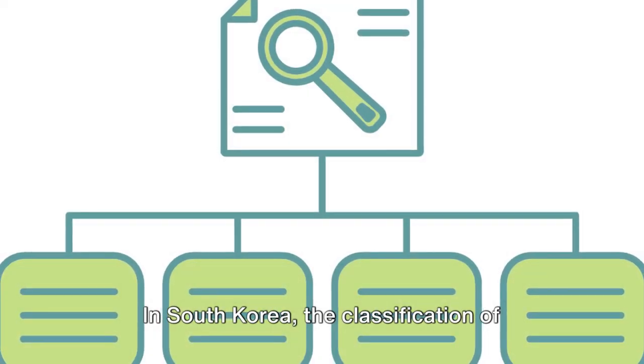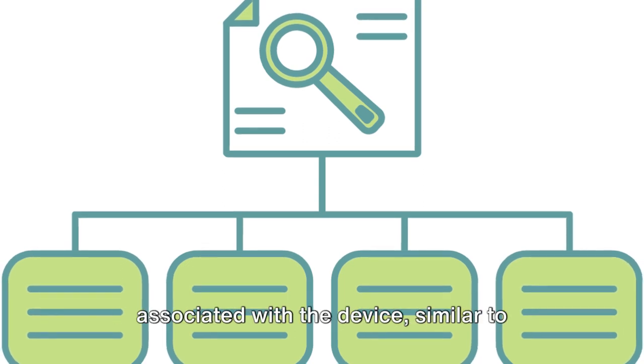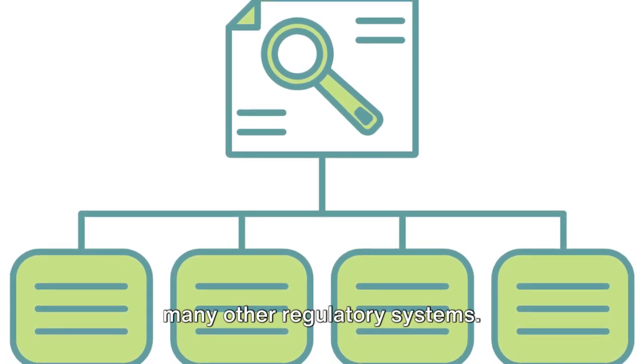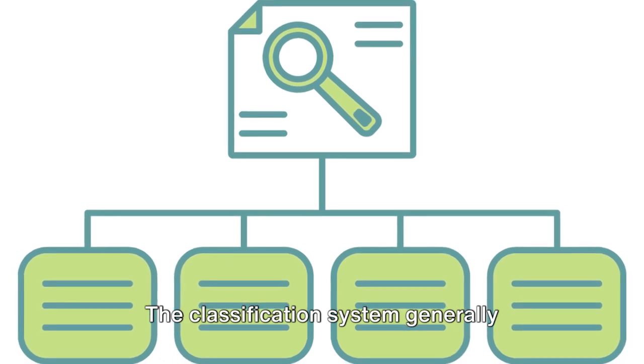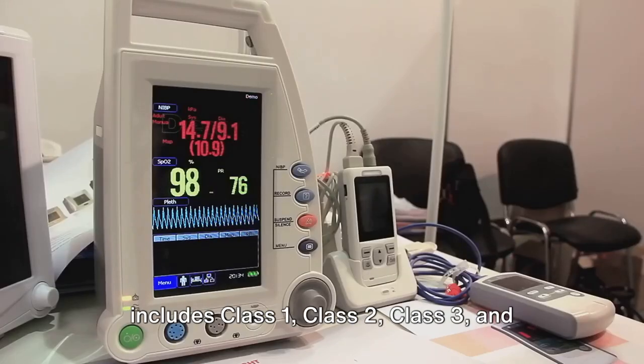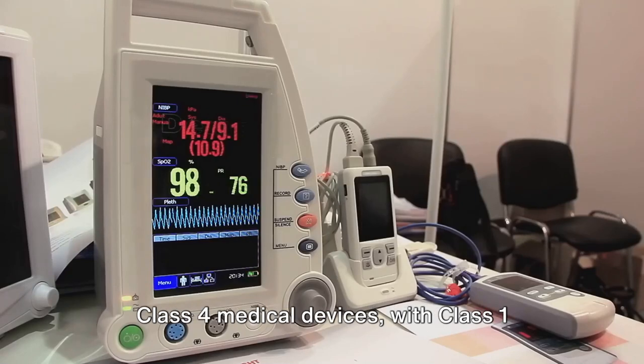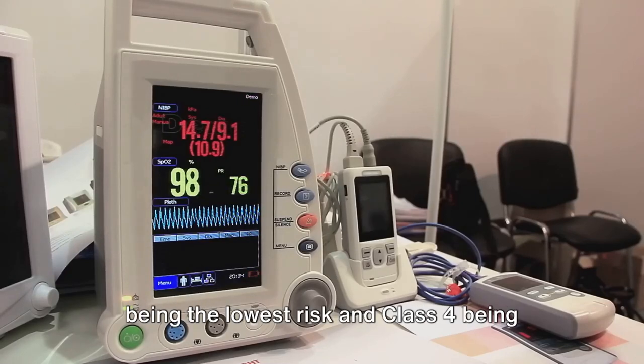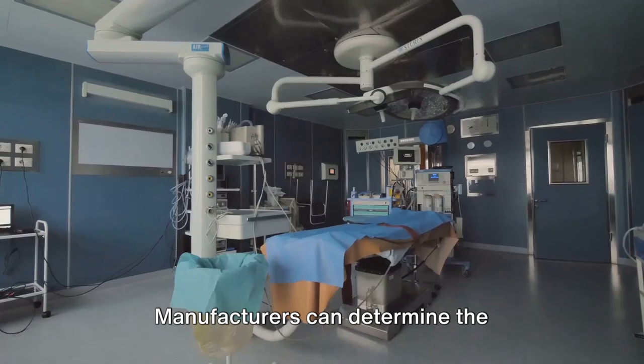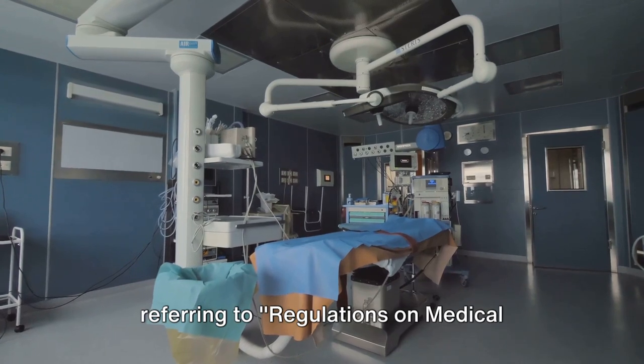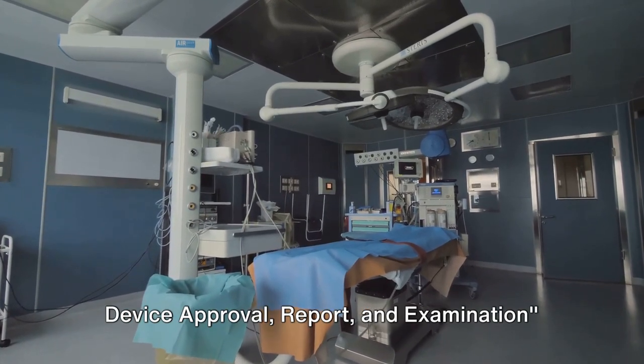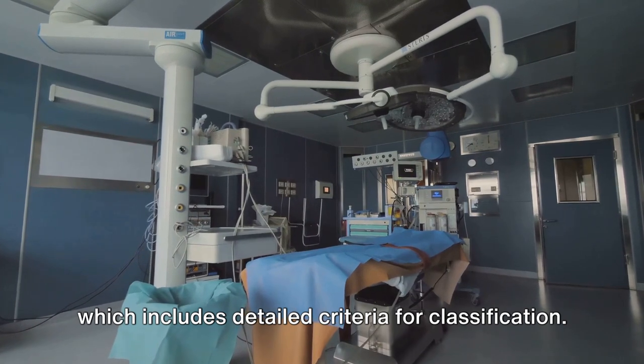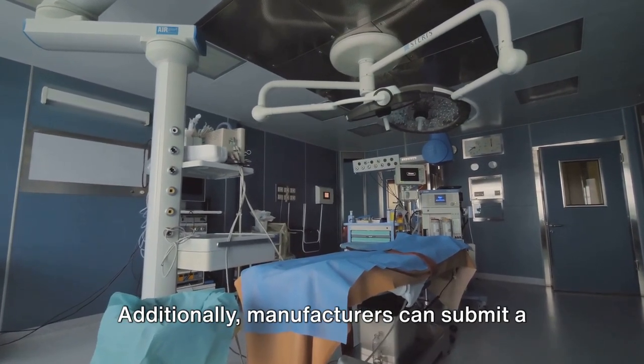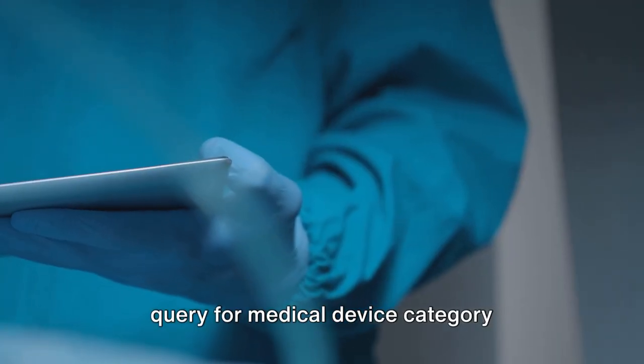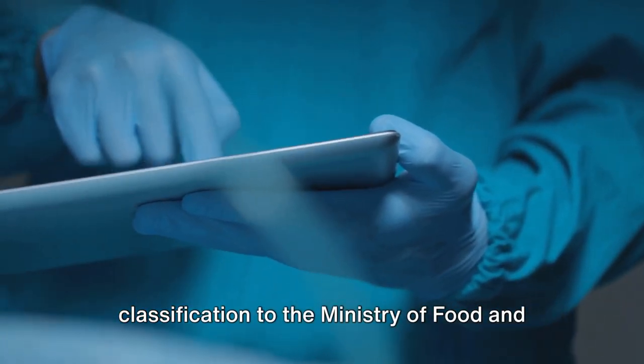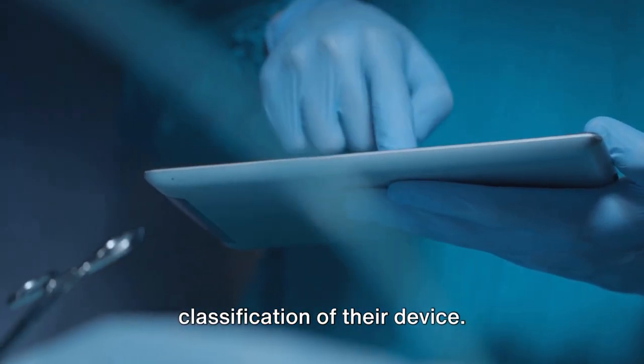In South Korea, the classification of medical devices is determined by the risk associated with the device, similar to many other regulatory systems. The classification system generally includes Class 1, Class 2, Class 3, and Class 4 medical devices, with Class 1 being the lowest risk and Class 4 being the highest risk. Manufacturers can determine the classification of their device by referring to Regulations on Medical Device Approval, Report, and Examination, which includes detailed criteria for classification. Additionally, manufacturers can submit a query for medical device category classification to the Ministry of Food and Drug Safety to determine the classification of their device.